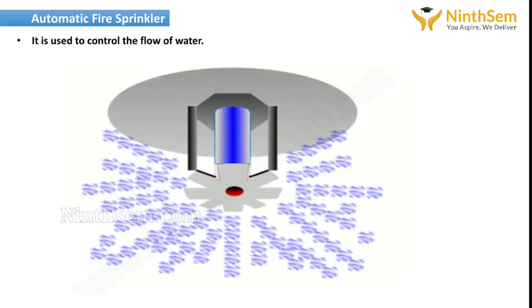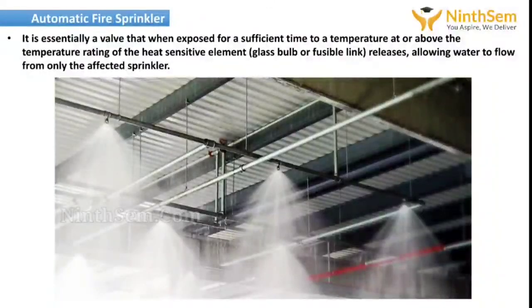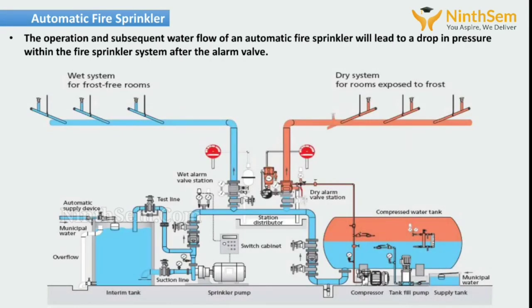Next, the automatic fire sprinkler. The fire sprinkler is also used to control the flow of water. It is essentially a valve that, when exposed for a sufficient time to a temperature at or above the temperature rating of the heat sensitive element, which is a glass bulb or fusible link, releases, allowing water to flow from only the affected sprinkler. And the operation and subsequent water flow of an automatic fire sprinkler will lead to a drop in pressure within the fire sprinkler system after the alarm valve.